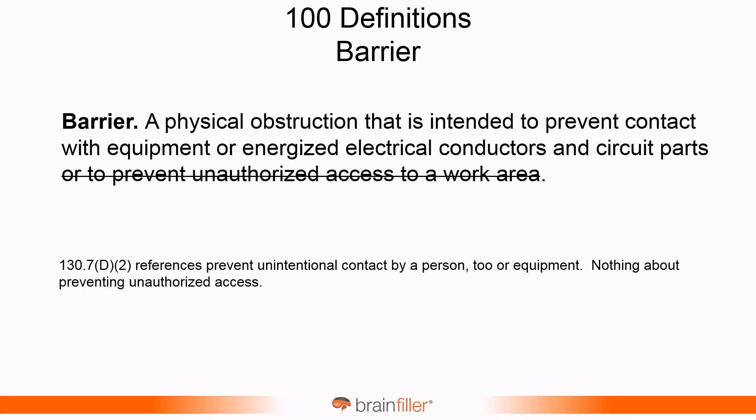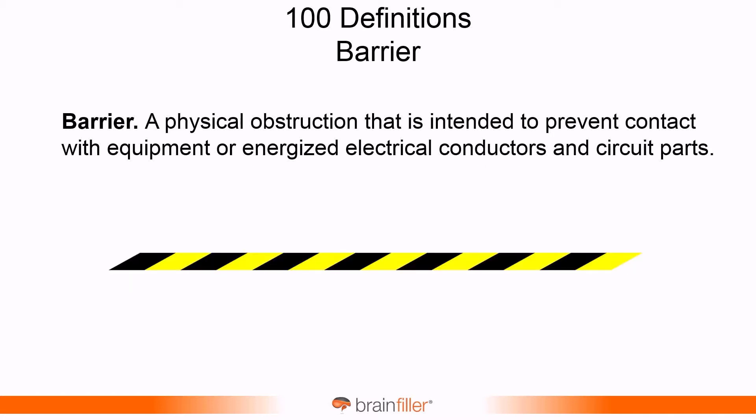The definition of 'barrier' was also changed to align with other references within NFPA 70E. The previous wording ended with 'to prevent unauthorized access to a work area,' which wasn't really what a barrier is about. It's about preventing contact with equipment or energized electrical conductors. So the definition for barrier now states it's an obstruction intended to prevent contact with equipment or energized conductors and circuit parts.